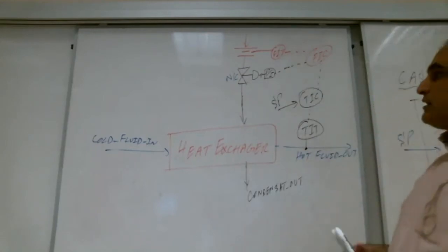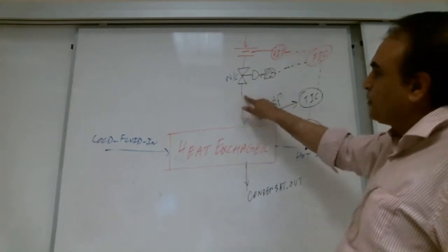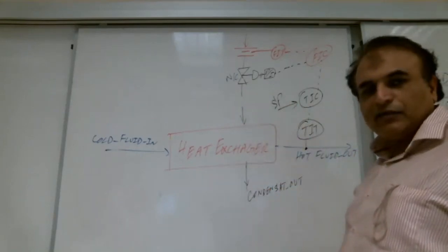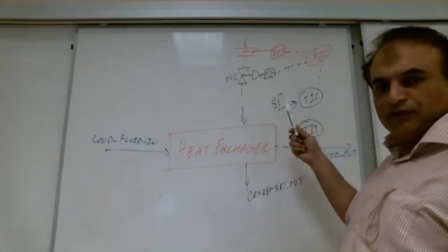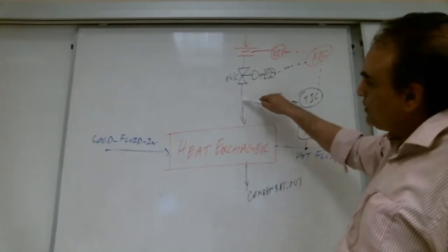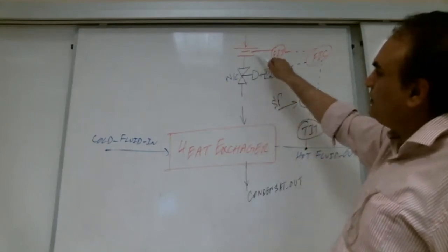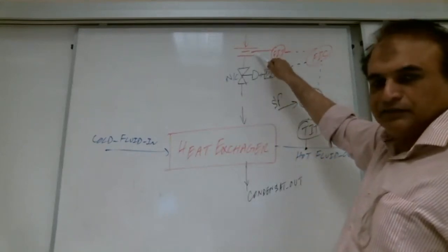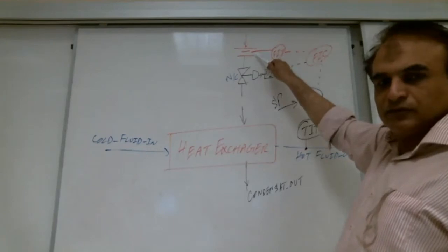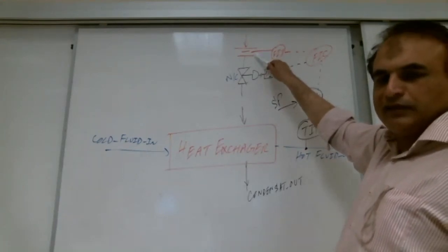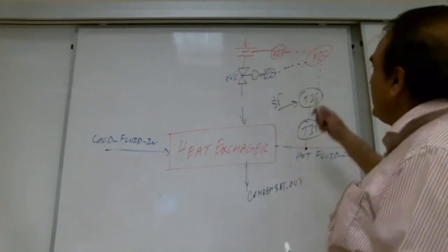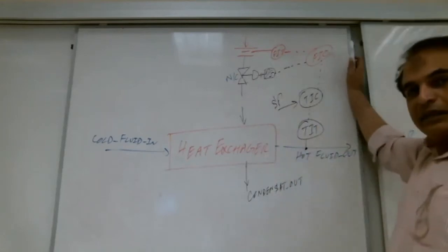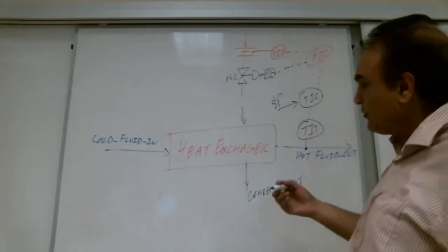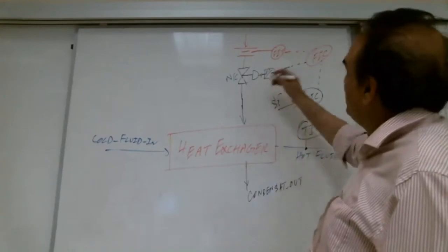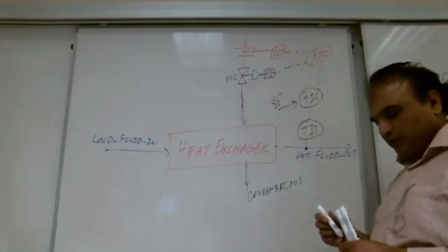Okay, Shabab, what was the first problem there? If the pipe is broken, there was no way the controller can know it, right? Before, yes. Now, if this pipe is broken, what this transmitter will read? What this sensor will read? 0. Very good. Brother Ali is writing 0. Very good. So right away this controller will understand the pipe has broken. A lot of other brothers now writing mashallah.